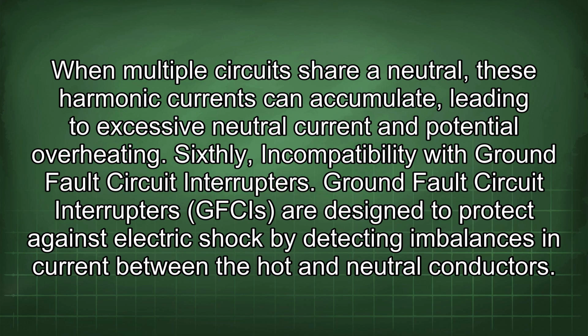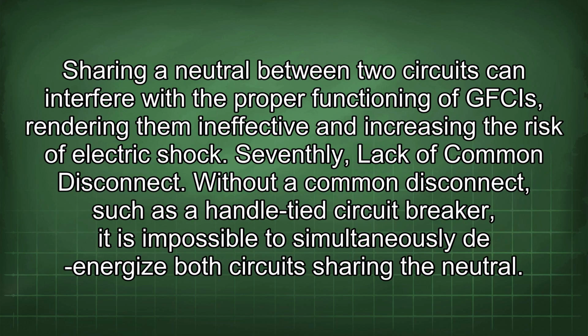Sixthly, incompatibility with ground fault circuit interrupters. Ground fault circuit interrupters (GFCIs) are designed to protect against electric shock by detecting imbalances in current between the hot and neutral conductors. Sharing a neutral between two circuits can interfere with the proper functioning of GFCIs, rendering them ineffective and increasing the risk of electric shock.